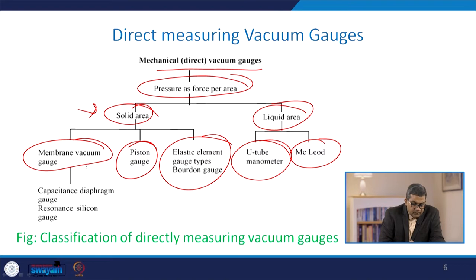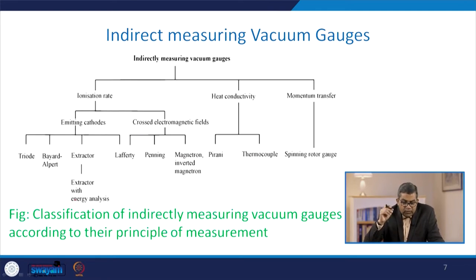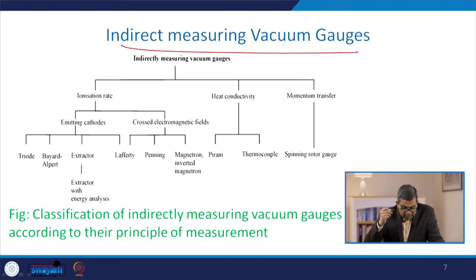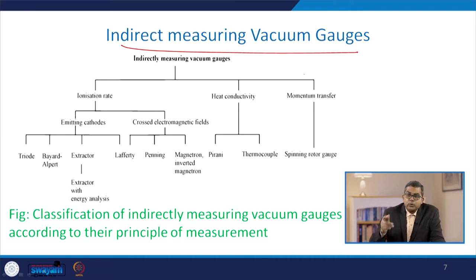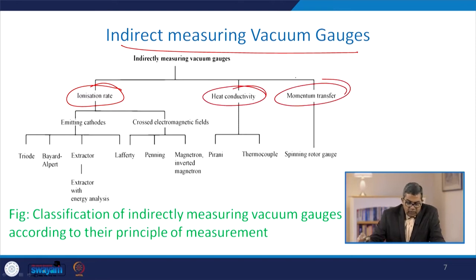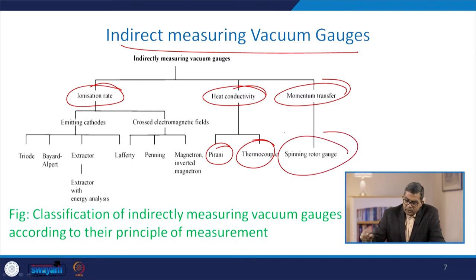Indirect measuring vacuum gauges are classified according to their principle of measurement into three categories: ionization rate, heat conductivity, and momentum transfer. Heat conductivity is further subdivided into the Pirani gauge and the thermocouple gauge, whereas momentum transfer refers to the spinning rotor gauge.